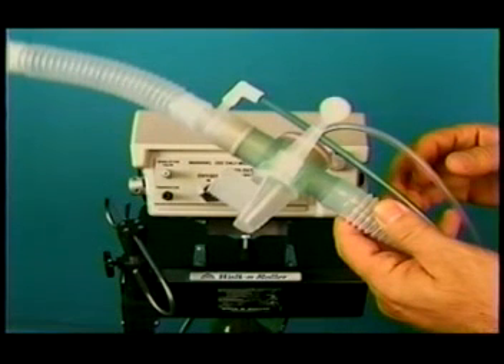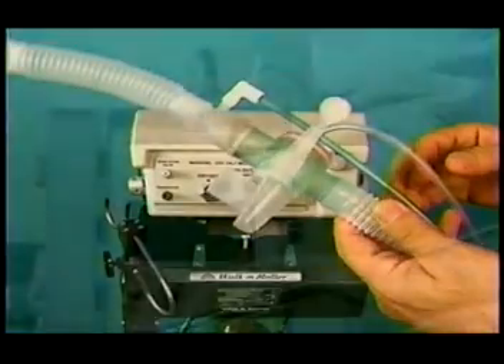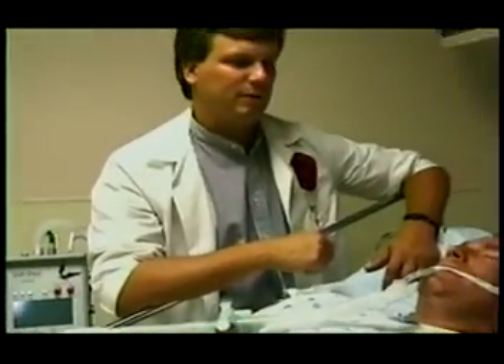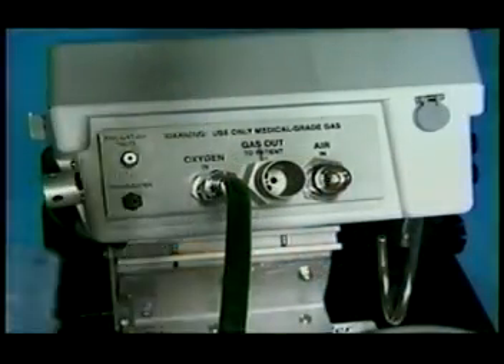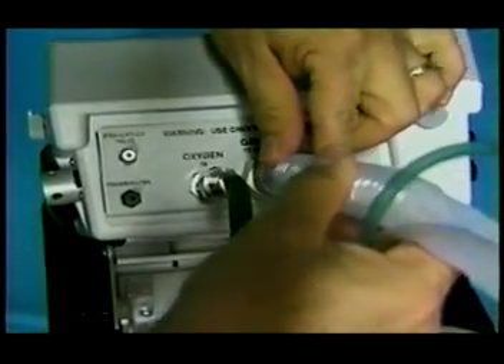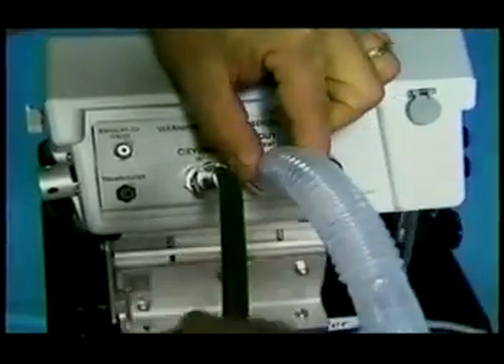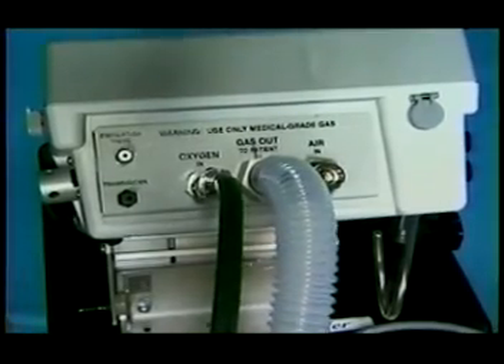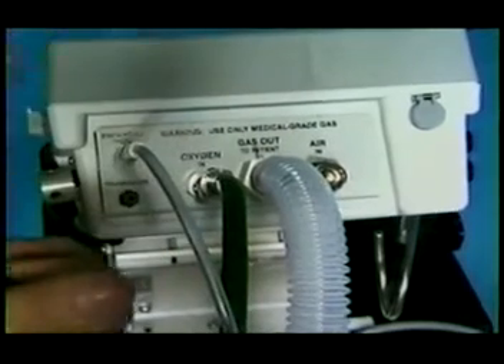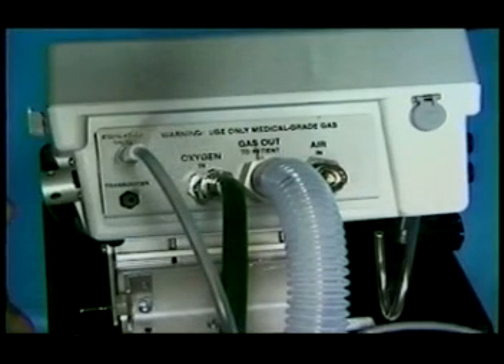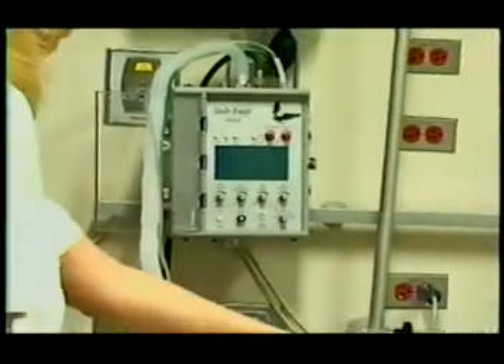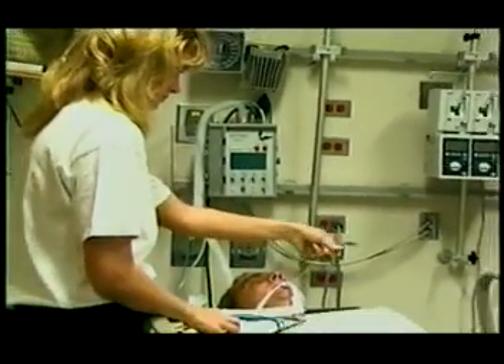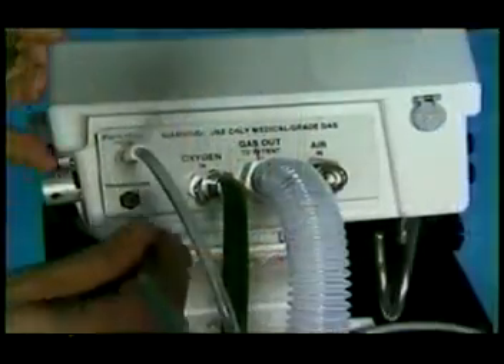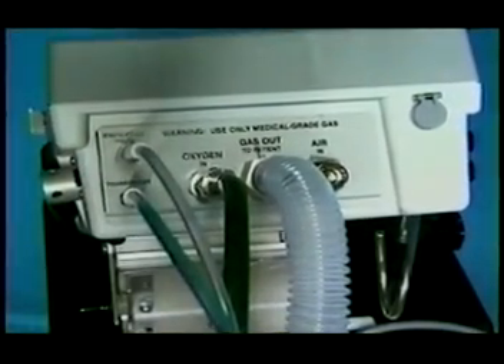The disposable ventilator circuit consists of several hoses, an exhalation valve assembly, and a patient connector. The large 22mm hose provides gas from the ventilator to the patient. It connects to the ventilator fitting labeled gas out to patient. Small diameter translucent hose provides controlling gas from the ventilator to the disposable ventilator circuit exhalation valve. It connects to the ventilator's clear, uncolored aluminum hose barb labeled exhalation valve. A small diameter green hose is used to monitor pressure signals near the patient's airway. It connects to the ventilator's green hose barb labeled transducer.